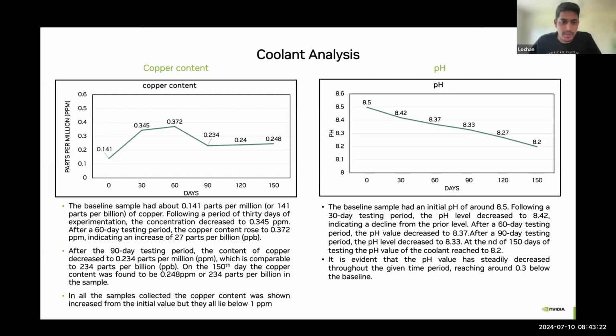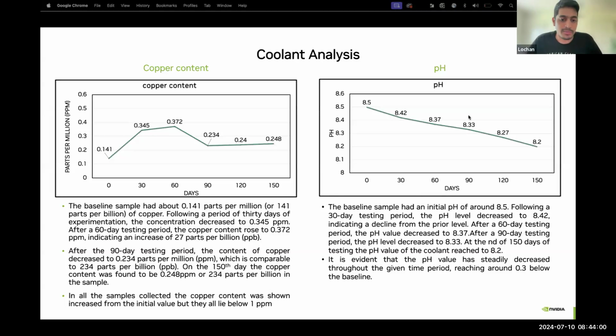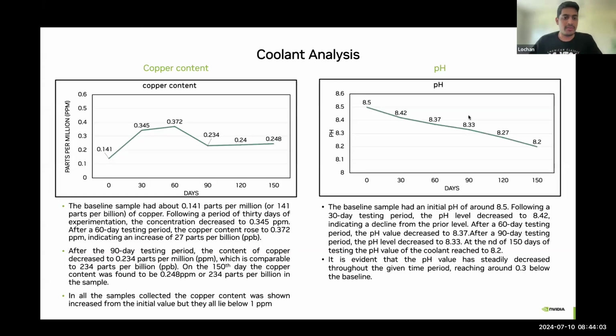liquid. And that's for regular data center scenarios where the flow rates are much lower than what we are running here. Usually in a data center, cold plates might go up to 1 LPM or 1.5 LPM maximum. But in our case, we are going around 7.8 LPM, which is way higher than the current standard followed in data centers. So at this level, we were expecting the copper content to be even higher than the 2 to 3 ppm they recommended. But overall, we observed that the copper concentration in the coolant was below 1 ppm for the 150 days of testing at high flow rates.